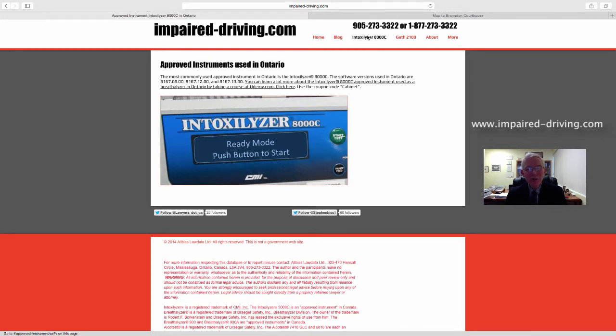The most commonly used approved instrument in Ontario is the Intoxilyzer 8000C. This breath instrument uses infrared technology. Breath is blown into the instrument through a tube and then to a sample chamber. Infrared light passes through the chamber and some of it is absorbed by the alcohol. The percentage of light absorbed is quantified and produces a signal that is converted into a reading.